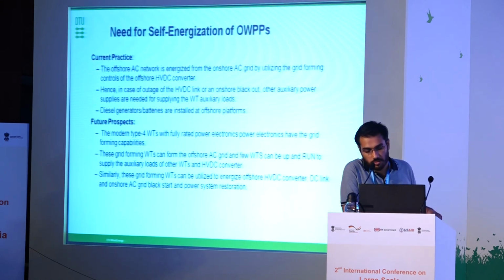Currently, the offshore AC network is energized from the onshore side by utilizing the grid forming capabilities of the offshore HVDC converter. Thus, in case of an outage on the onshore side, auxiliary power supply, which is mostly diesel generators, sometimes batteries, is used at the offshore platforms to power up the auxiliaries and then get the wind turbines running. However, modern Type 4 wind turbines, which have fully rated power electronic systems and, in the future, hopefully grid forming capabilities, can energize the offshore collector grid, power up the auxiliaries, deal with the charging requirements of the cables, and then charge the converters and the HVDC link, and finally provide power system restoration services.